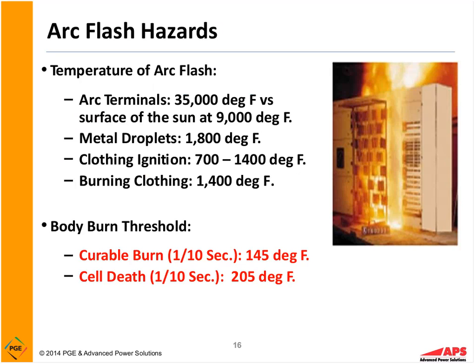So when we look at the temperature of an arc flash, this is hot stuff. Arc terminals, this is actually measured in labs, such as Mersen Labs, which has an arc testing lab, and Kinectrics; several arc testing labs are available to do the arc testing. They measure the temperature at the arc source, 35,000 degrees, versus the surface of the sun at 9,000 degrees. Now, I'm not sure who took that measurement. One of the classes I was teaching said it was an apprentice, and they've never seen him since. Now, I know that's not true, but it just seems kind of funny, to some people at least.